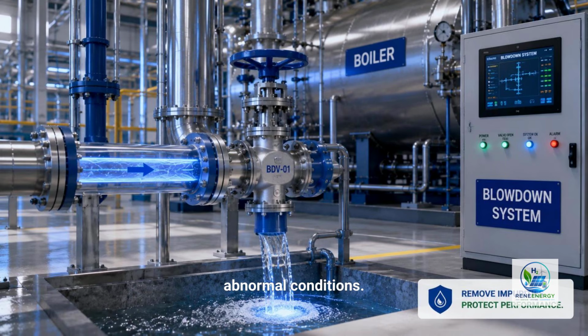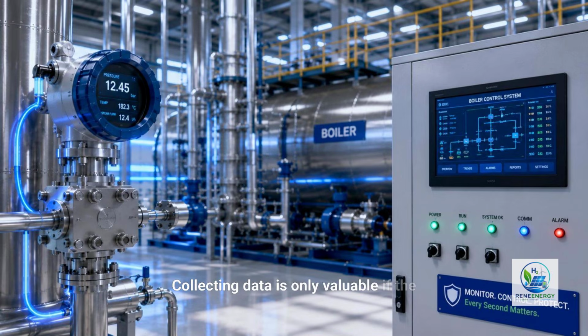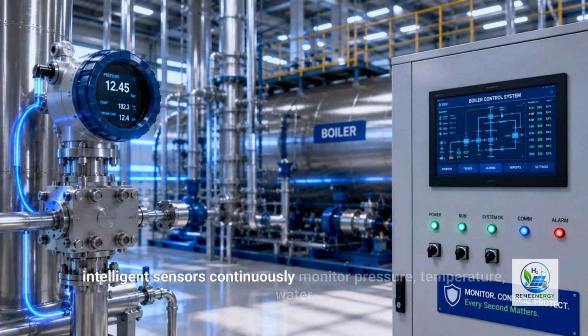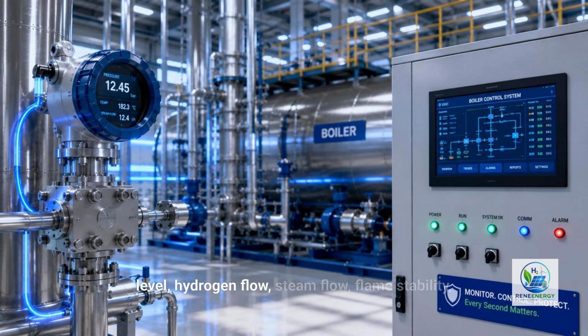Collecting data is only valuable if the system can respond to it. Throughout the hydrogen boiler plant, hundreds of intelligent sensors continuously monitor pressure, temperature, water level, hydrogen flow, steam flow, flame stability, and equipment health. Every second, these sensors generate thousands of measurements that provide a complete picture of the boiler's operating condition. If a parameter begins to move outside its optimal range, the control system reacts almost instantly.